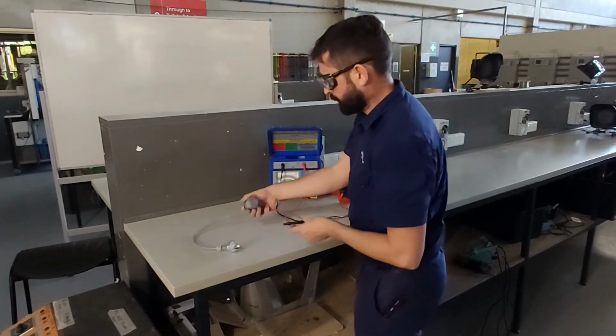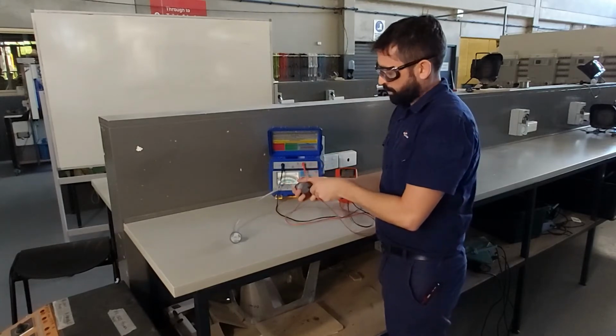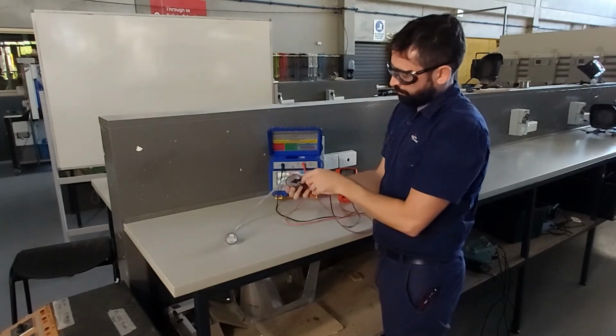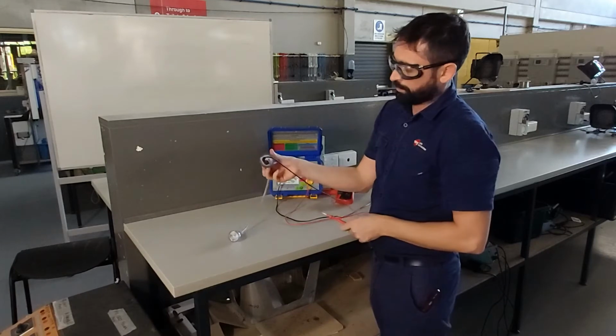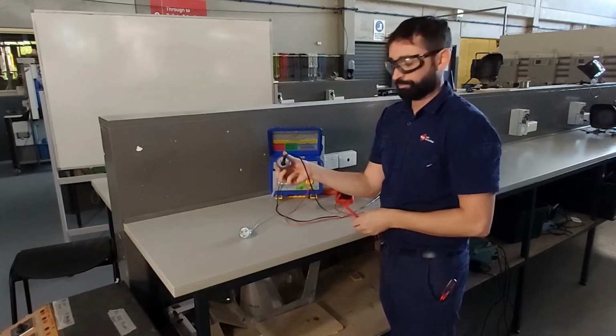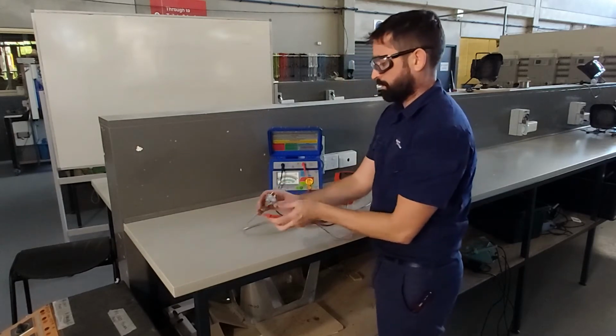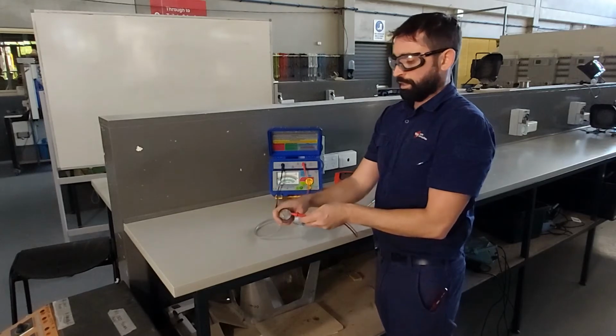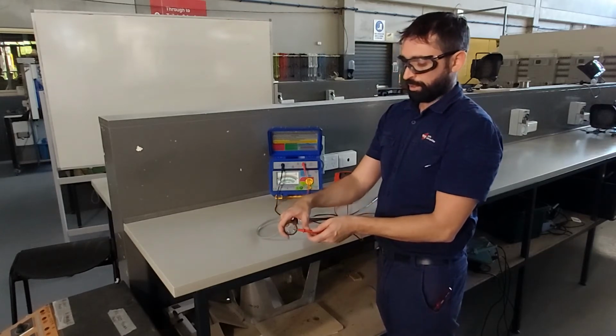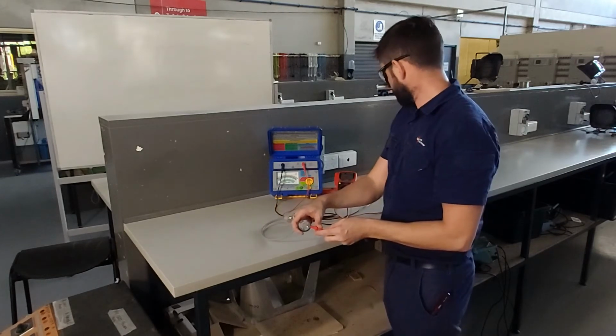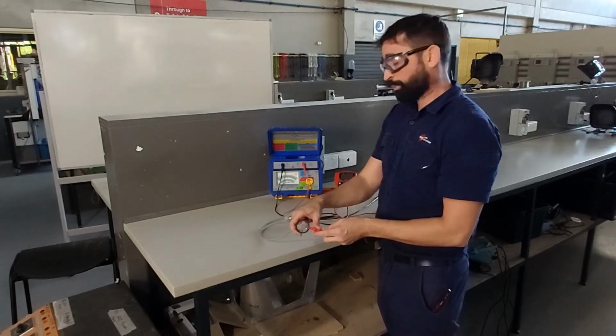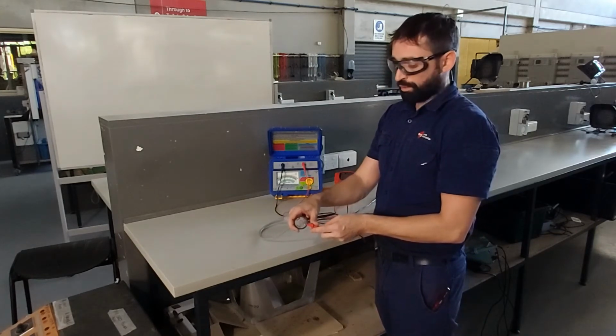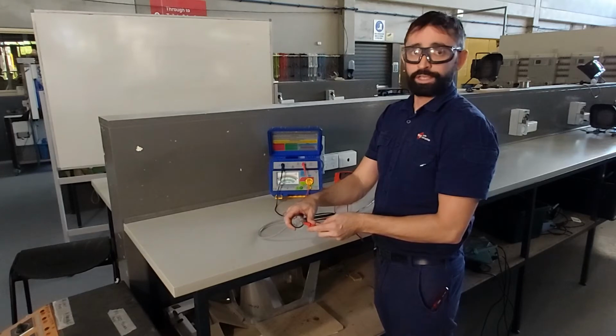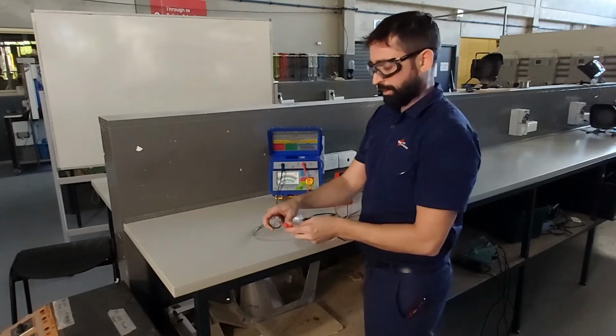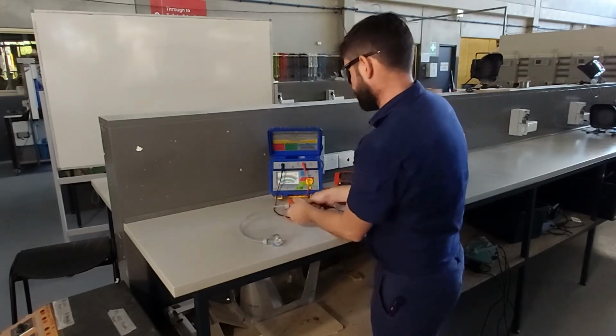And then we're simply going to put one probe into the earth terminal, which is the bottom terminal, like this, like so. And then we're going to put our next probe across the earth terminal on the plug end. Now I'm getting 0.0 ohms, and what we're looking for is 1 ohm or less for an extension cord. So that's pretty good. That's what we want.